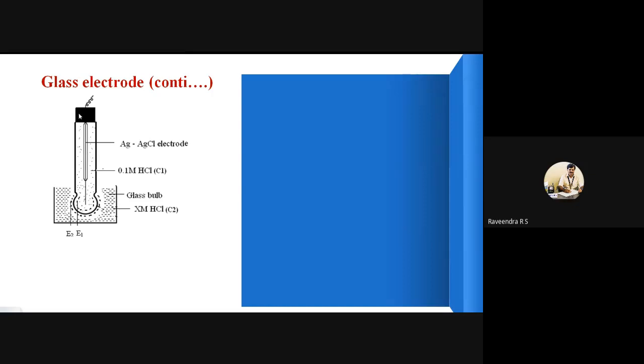As shown in the diagram, this is a long glass tube with a sensitive thin-walled glass membrane at the bottom — a small bulb at the end of the glass tube. The tube contains 0.1 molar hydrochloric acid at concentration C1. A silver/silver chloride electrode is immersed in the hydrochloric acid, serving as the external electrical connector. The entire glass electrode is then dipped in an unknown concentration of hydrochloric acid — X molar.